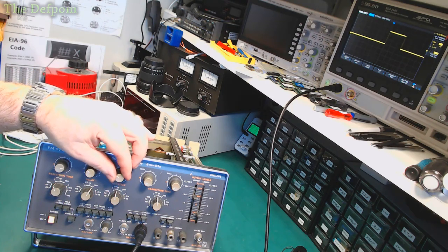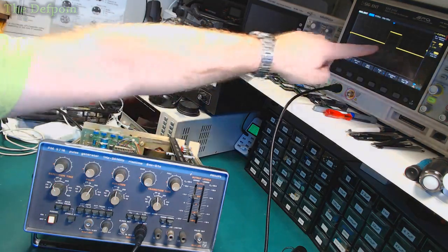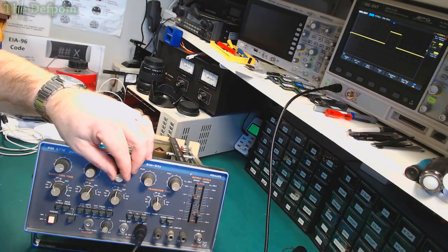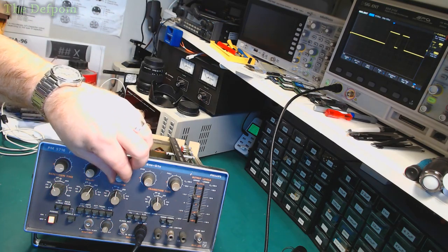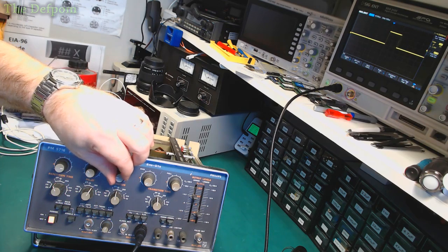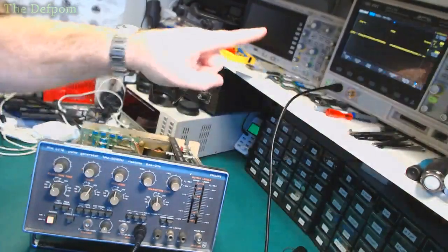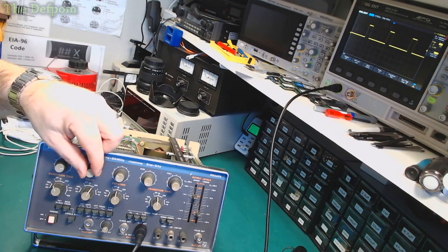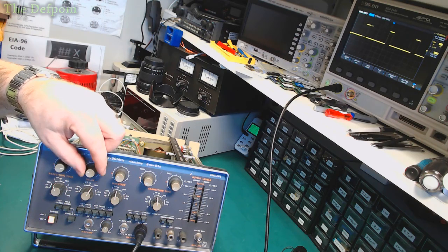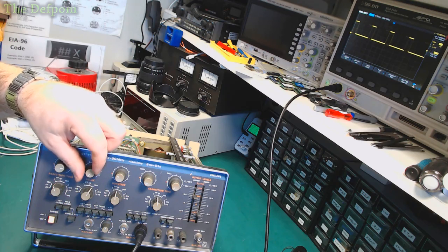So when I've got a duration set long enough, there is only 1 pulse. Now when I get down a bit short, right next to it right now I'm getting 1 pulse. And as I bring it down further, a second pulse turns up at the same point. So it seems like there's probably a bad capacitor there, smoothing that out or something. Once I get to a certain point, I've got the correct pulse, a single pulse. There is some jitter. Could be dirty control. Yeah, probably dirty control. Could be.